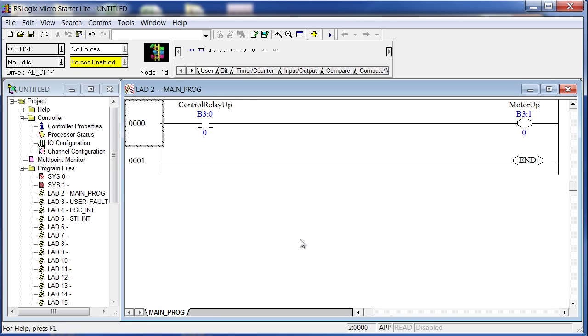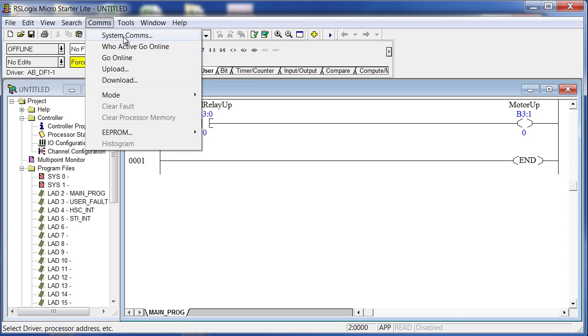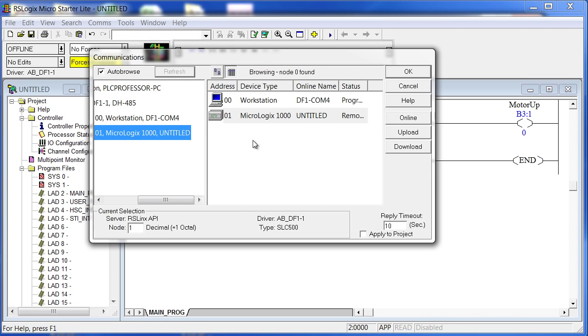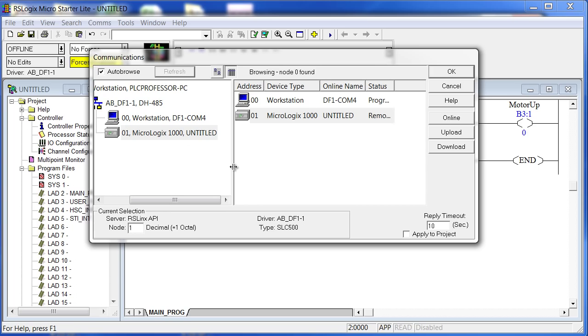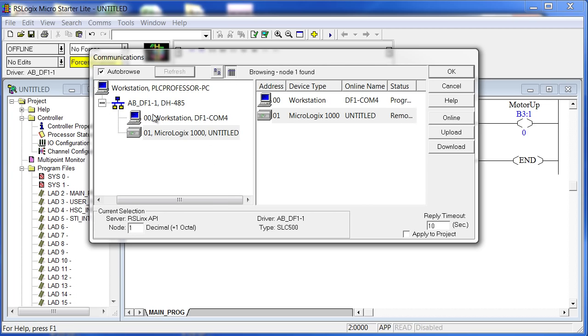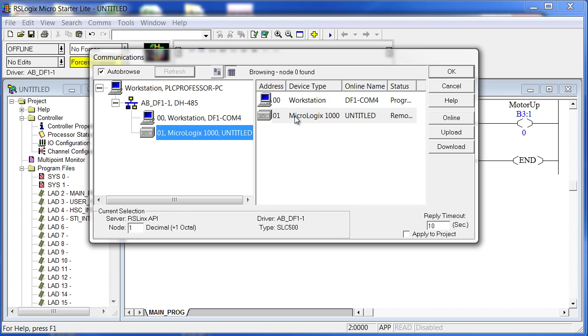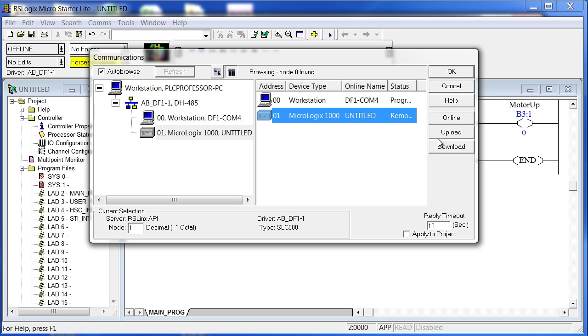When you use Verify Rung or Verify File or Verify Project, you're telling RSLogix 500 to check your syntax and structure — not whether it does what you want, just whether it's in an acceptable format supported by the software. Now we're going to download. Go to Comms > System Comms. I'm assuming you already have an RS Linx driver configured — I already have mine configured and it sees the processor.